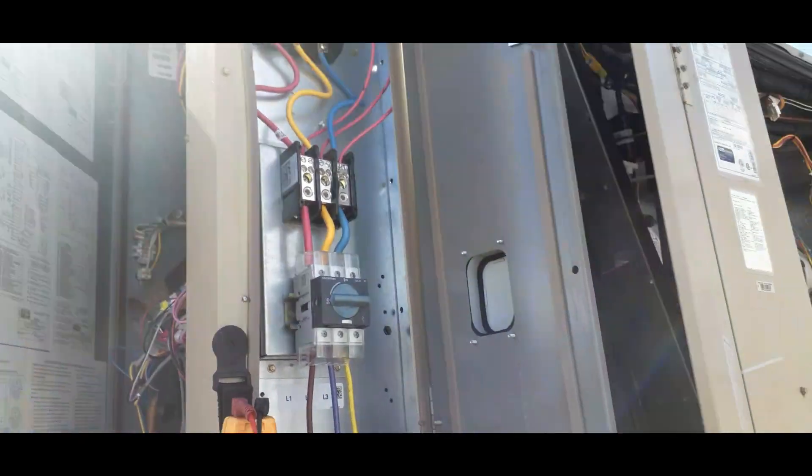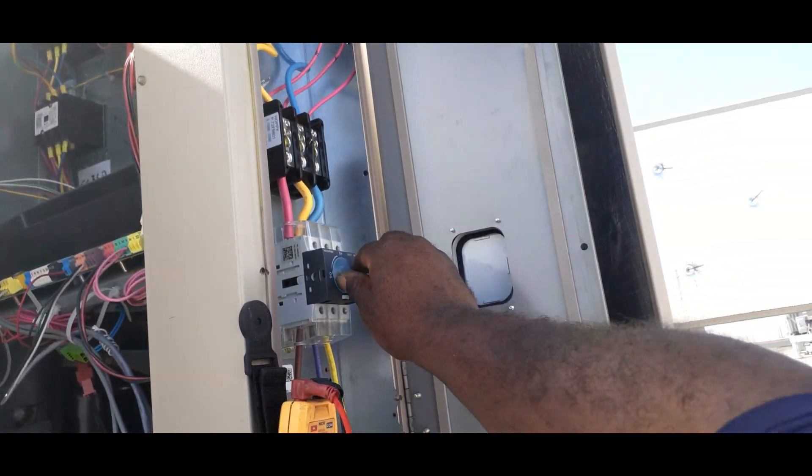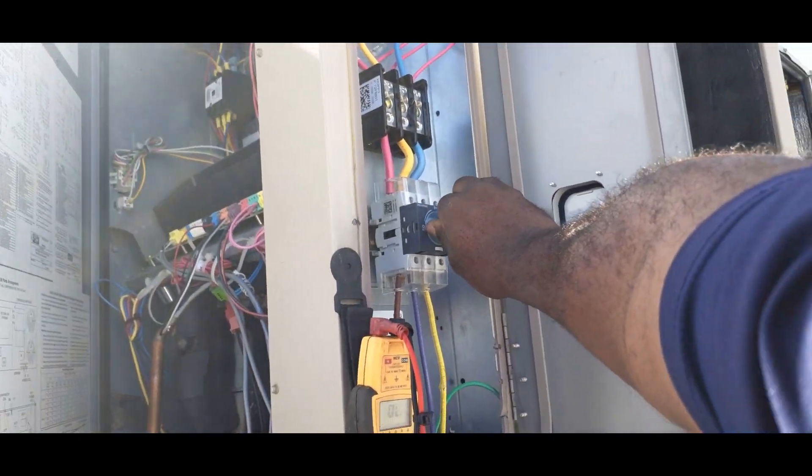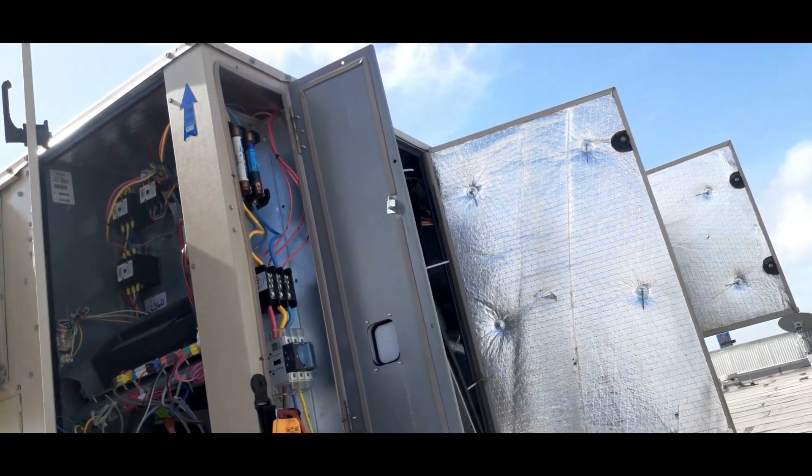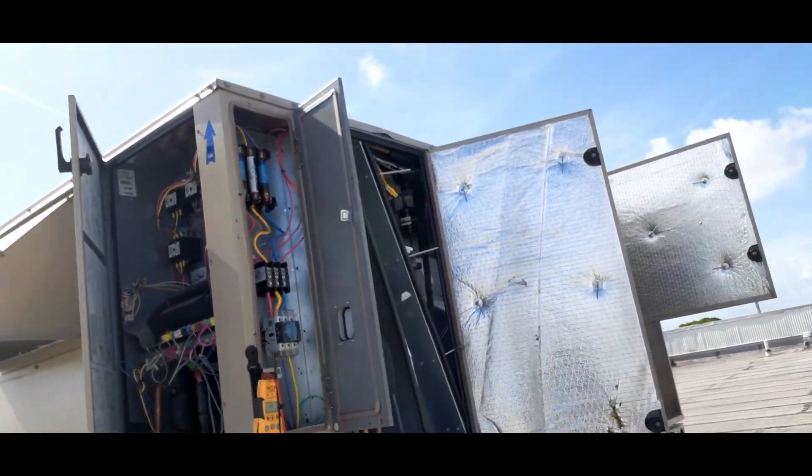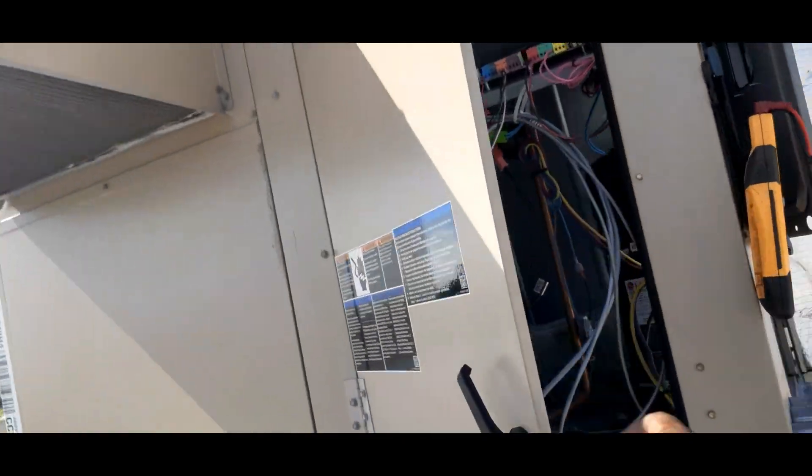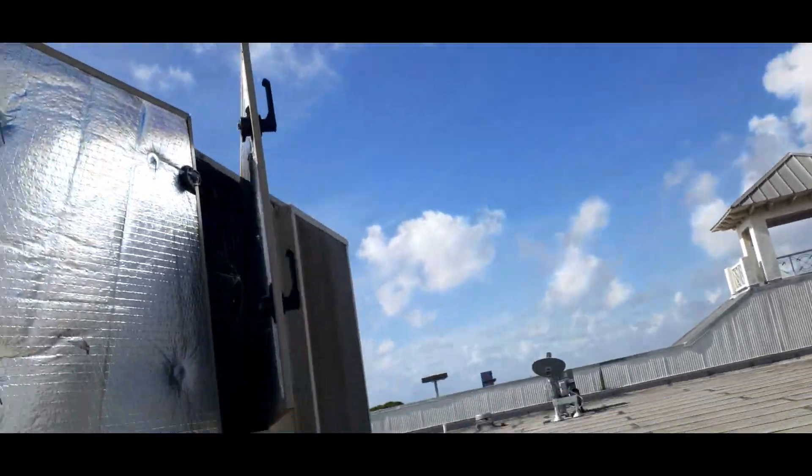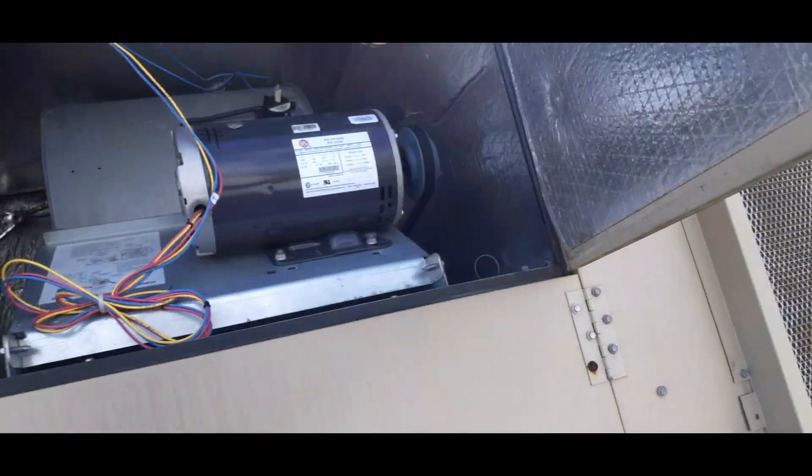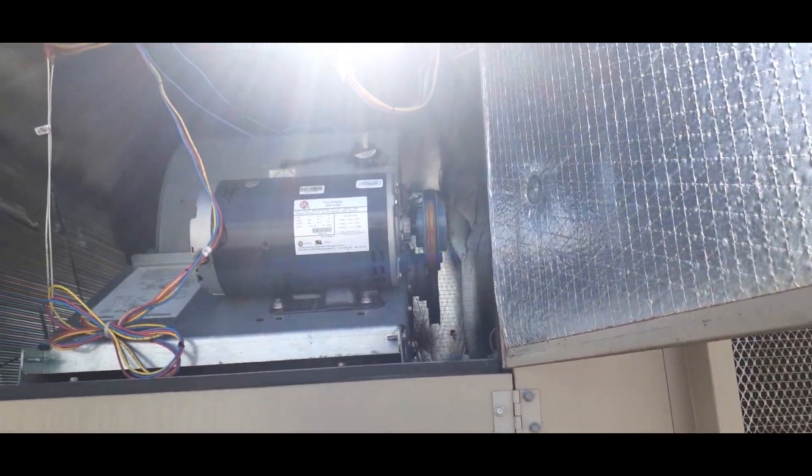All right, so everything is connected. I just put that fuse in. This is 480 volts, so I'm gonna kind of just extend back a little bit and I'm gonna flip this on. All right, I didn't see no smoke come out of the fuse or anything like that. Came on. Look at that. Belt spinning in the correct rotation.